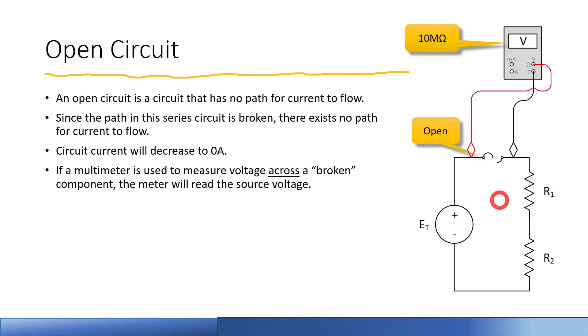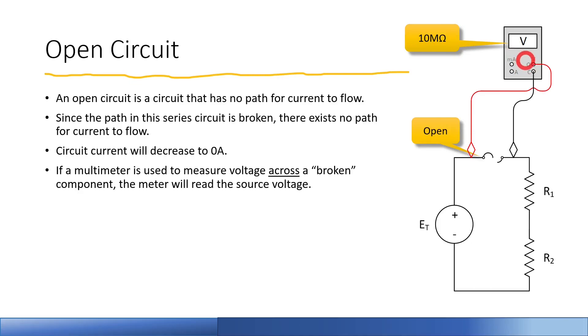If the fuse is good, we will actually read zero volts, because most current passes through the fuse since it has significantly less resistance than the meter's 10 megaohms. So you don't have to pull the fuse out to test it — which is very practical in the field, since pulling a fuse from running equipment could unnecessarily take a line down. We'll prove this out in a shop exercise.